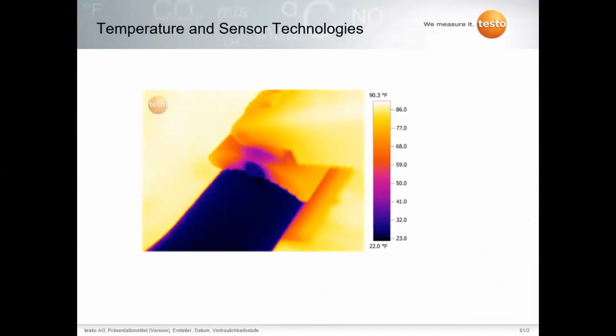And just like anything else when we're measuring temperature, there's an element in that pipe clamp probe. This happens to be a thermal image picture of a suction line and a pipe clamp probe that's on the suction line. And you'll notice the different colors. In the thermal image, we manufacture thermal cameras as well, the difference in colors gives us a difference in temperature. These are extremely accurate measuring devices. The military uses thermal imaging quite a bit, law enforcement, of course, but we're also seeing a lot of thermal imaging now because it's now affordable in the HVAC market.